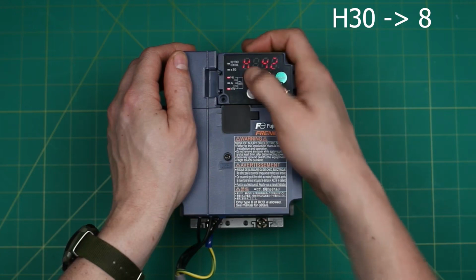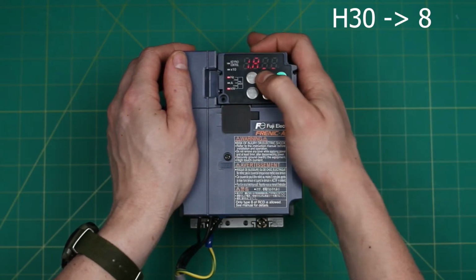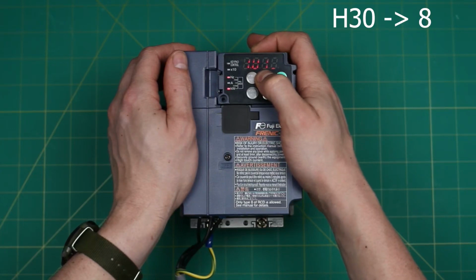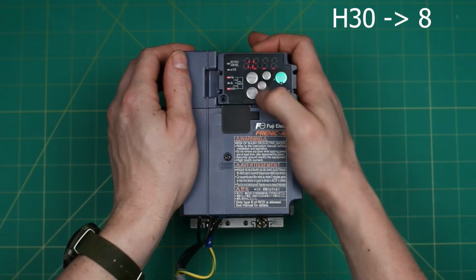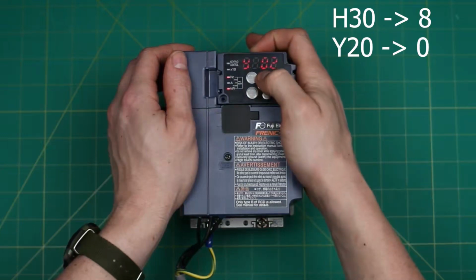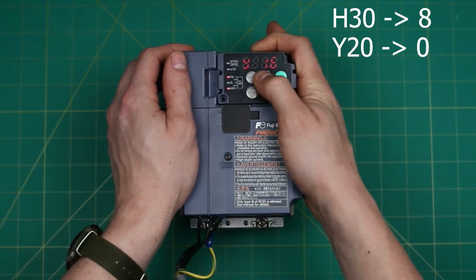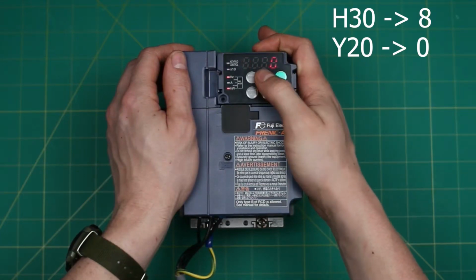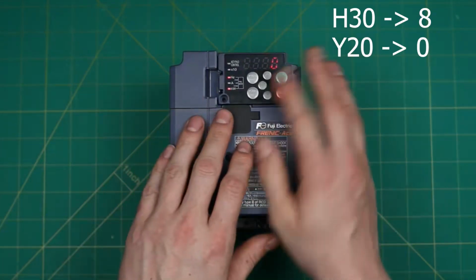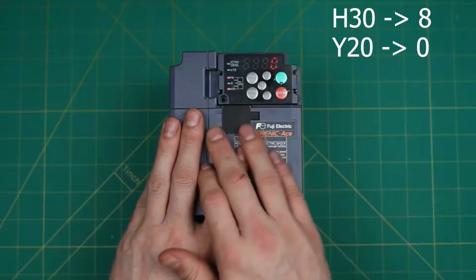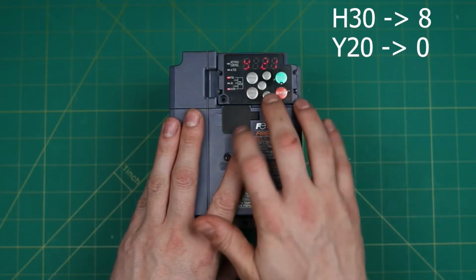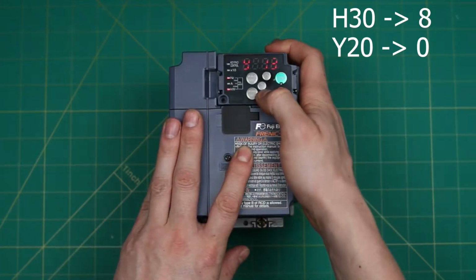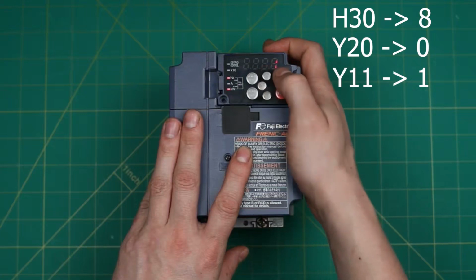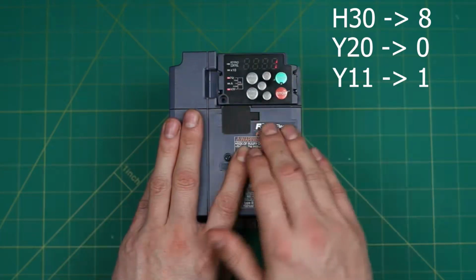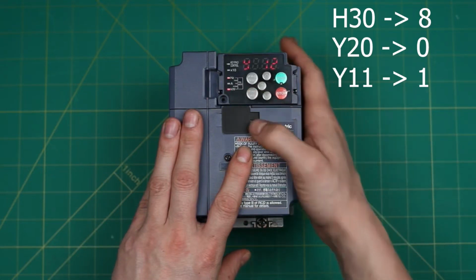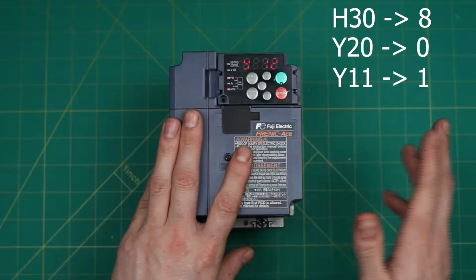Program. Go back up. Next is Y20. And Y20 needs to be set to 0. That 0 will set the comms protocol on port 2 to Modbus. And now, back to Y11. We need this set to 1. That sets the station number on the serial bus. Now that that's all set, we can go to configuring the HMI.